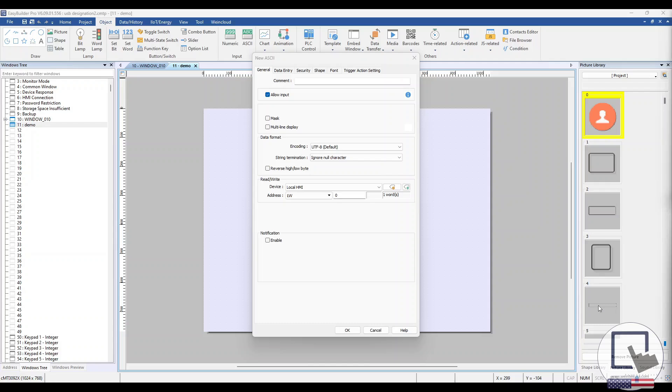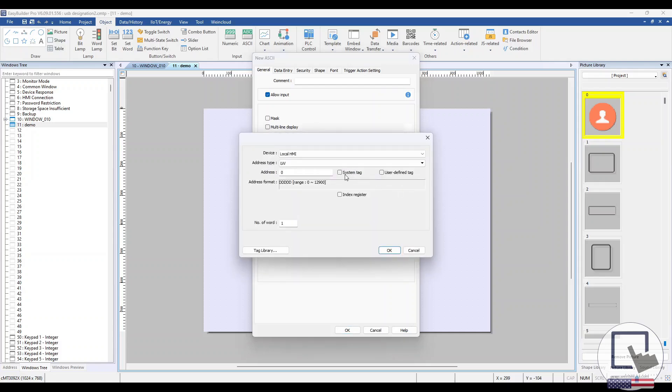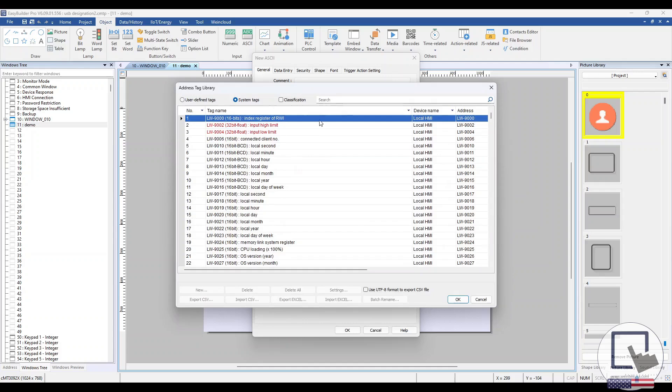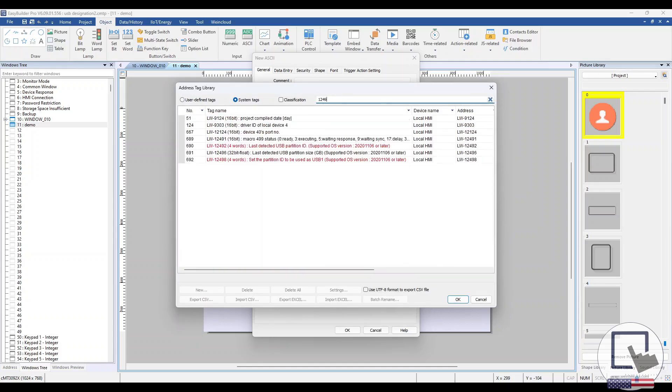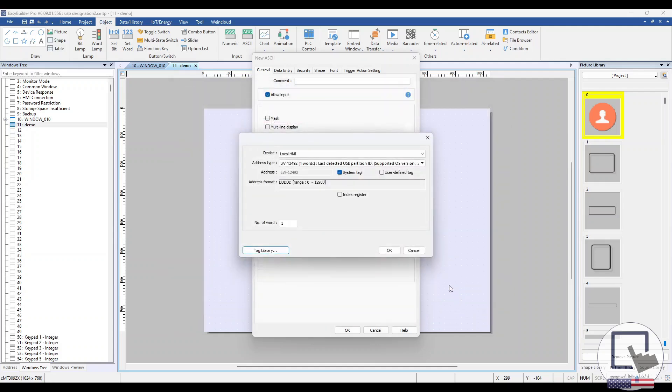Click the Settings button and select the System Tag option. Select the Tag Library button and enter the numbers 12492 into the search bar. Then, select the LW12492 Last Detected USB Partition ID system tag. The Partition ID is a unique identifier assigned to the USB drive. Let's change the number of words for the ASCII object to 4 and place the object within our project.